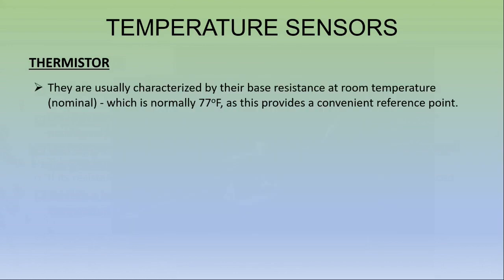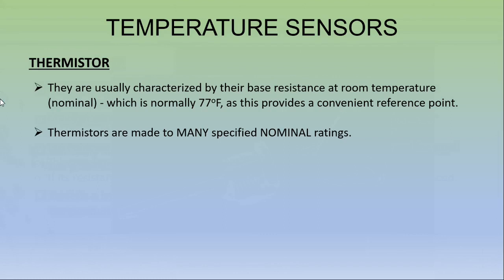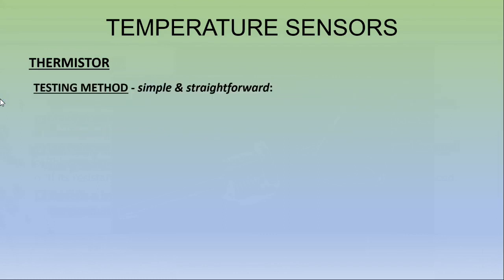Thermistors are usually characterized by their base resistance at room temperature nominal, which is normally 77 degrees Fahrenheit, as this provides a convenient reference point. Thermistors are made to many specified nominal ratings. As far as testing methods, it's also simple and straightforward.